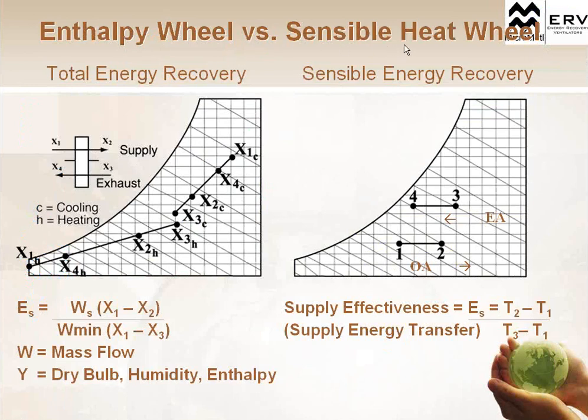Just a quick breakdown on enthalpy wheels versus sensible heat wheels. I mentioned heat recovery ventilators. There's also those sensible wheels. These actually just transfer your sensible energy, or affect the temperature in a space. So if you look on the right, obviously we're just moving along the sensible energy line of the psychrometric chart. We're just changing temperatures from 1 to 2. We're preheating or pre-cooling and not addressing any of the latent energy or the humidity in the space.